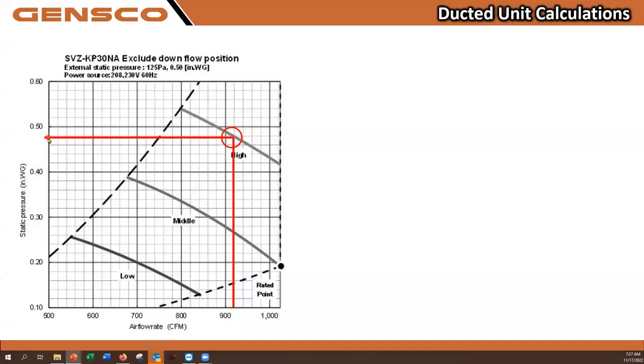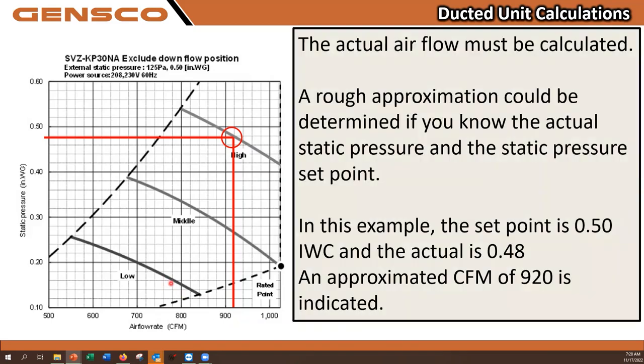So if I follow my actual static pressure line over to the high-speed fan curve, and where it intersects with the curve, goes straight down, this puts my actual CFM somewhere in the 920 CFM range. Now, this would be okay to use for a ballpark, but it's not going to be 100% accurate, because there is a little known phenomenon called the system effect.